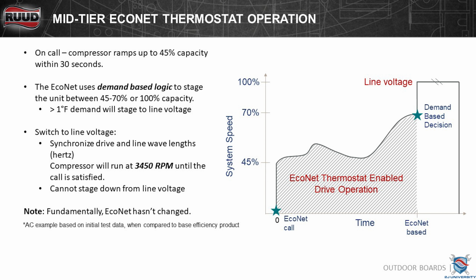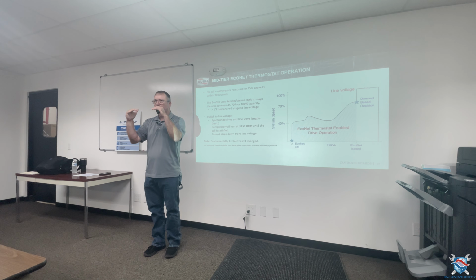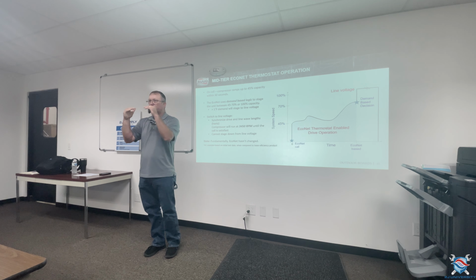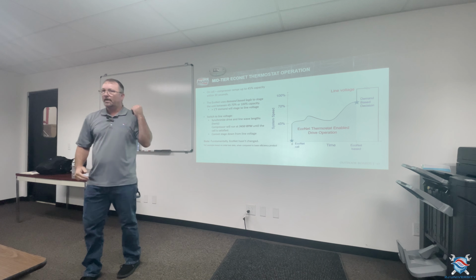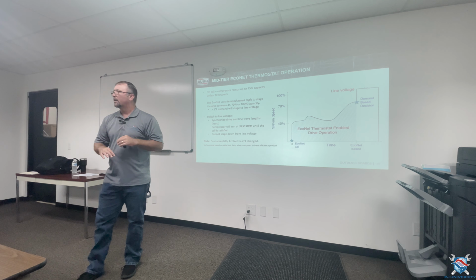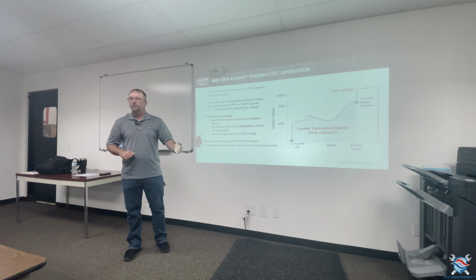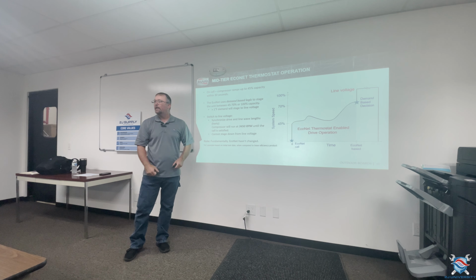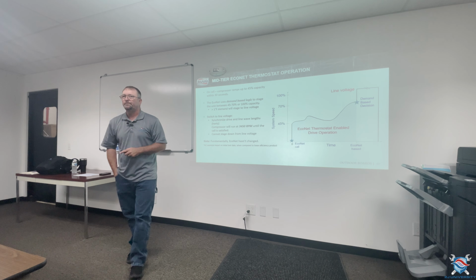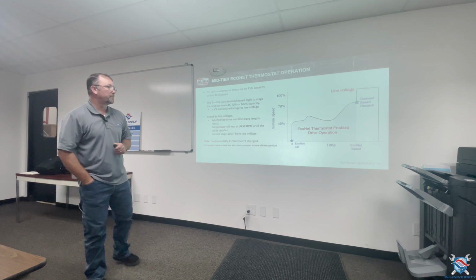Until it is equalized at that 70%, because that board knows at 70% capacity that the voltage on the inverter board should be 230 volts and my inrush is going to be 230 volts to get to that 100%. Until it hits that 70%, it knows that the voltage is lower, and that's why you don't want to inrush 230 volts immediately, or else it'll fry the board. Okay?